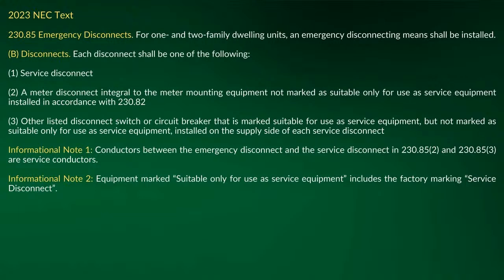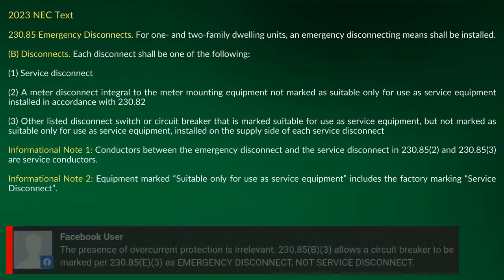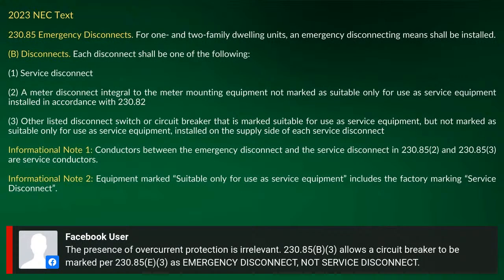Now, some may look at this and say, wait a minute, I can just put a disconnect out there with that overcurrent protection device. And some have said, well, I can come there and establish a grounding electrode system, and then I can come over here at the panel board and establish the grounding electrode system too. I would say that's where you get into a little problem when you look at 250.6 and you get into objectionable current through the system. Yeah, so I wouldn't agree with that either.